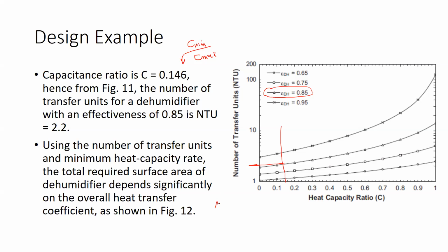The definition of number of transfer units, if you remember, is basically U into the area over Cmin. We know this value now. We know Cmin, we have calculated it. We are going to estimate an overall heat transfer coefficient of about 10 watt per meter square Kelvin. And then you can calculate from here what should be the surface area, which is the heat transfer surface area. If this surface area is going to be in the form of long tubes, then this is going to be, for example, pi dl. If you are going to do it with a number of tubes, then it will be n into pi dl.